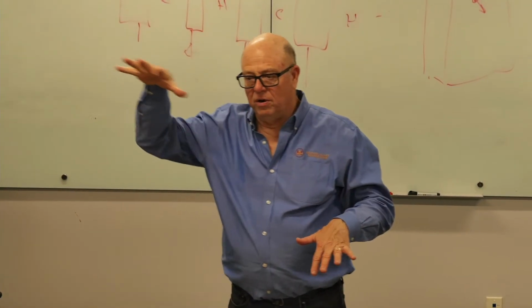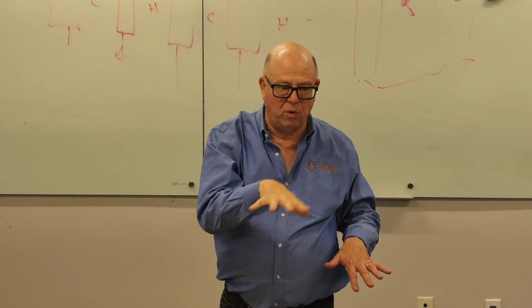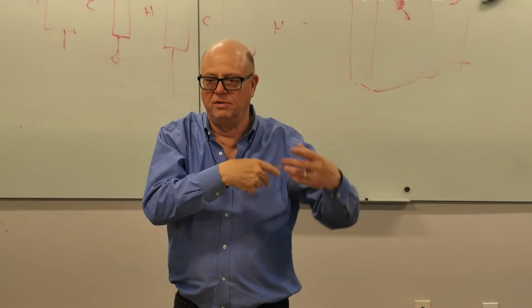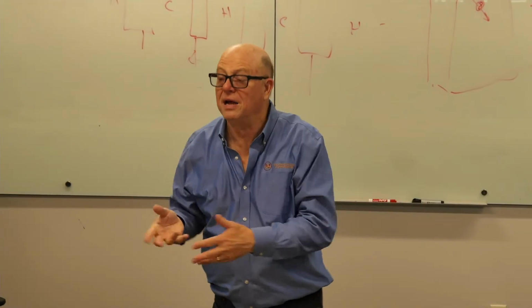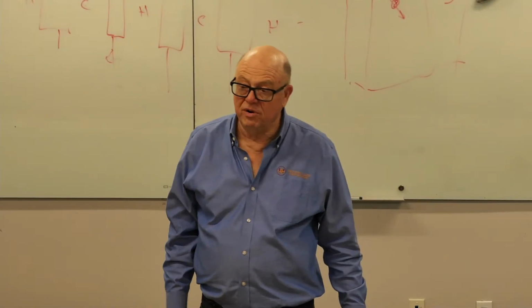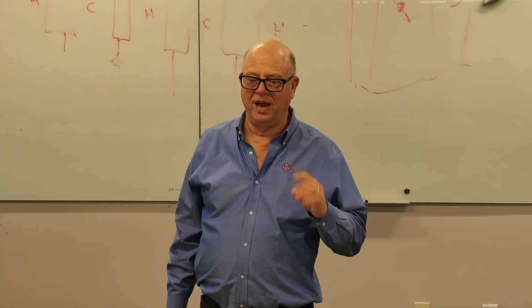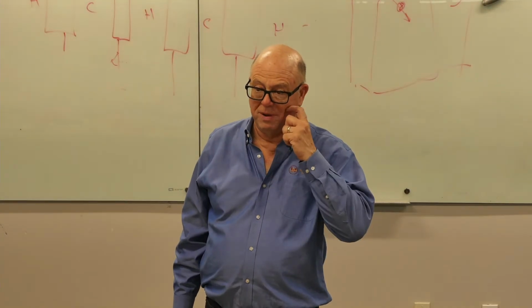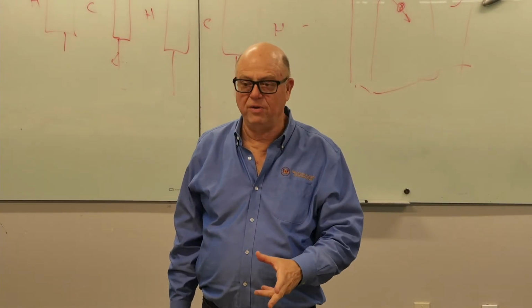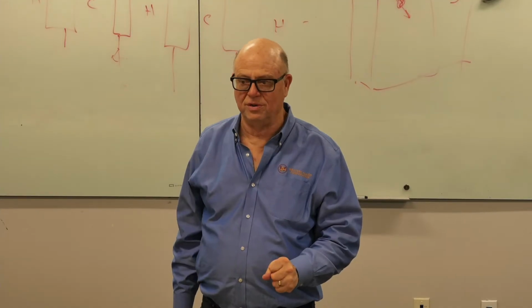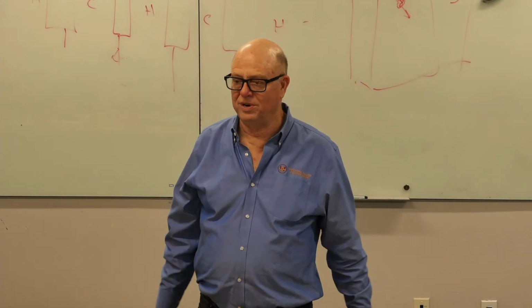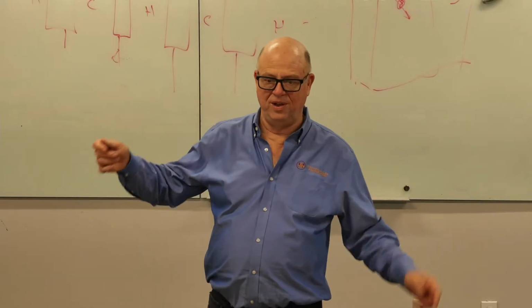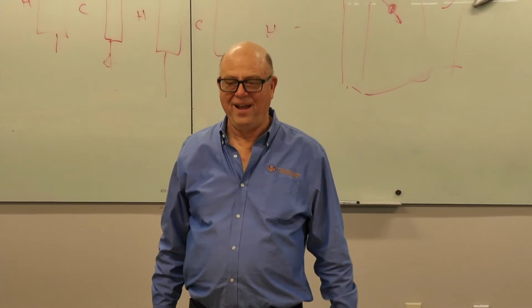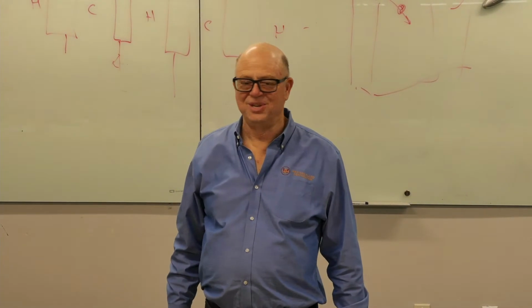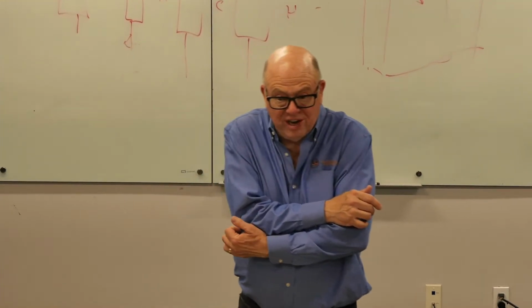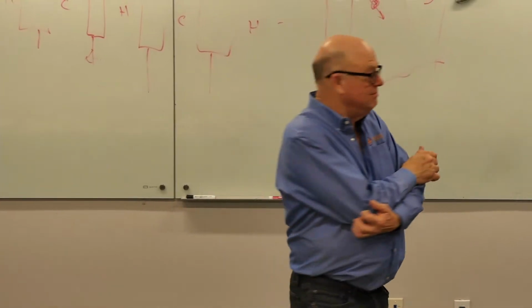You layer these breakers for individual levels of response. And so that was never done. And as it happened, the guy who had been the facilities manager for about a year, when they opened it, they hired the guy who project managed the electrical. So we had snow for 20 minutes during an NFL game until somebody found the main breaker and reset it. And he got fired the next day. So when you hear somebody say, we'll get snow and I'll get fired, that is how that works.